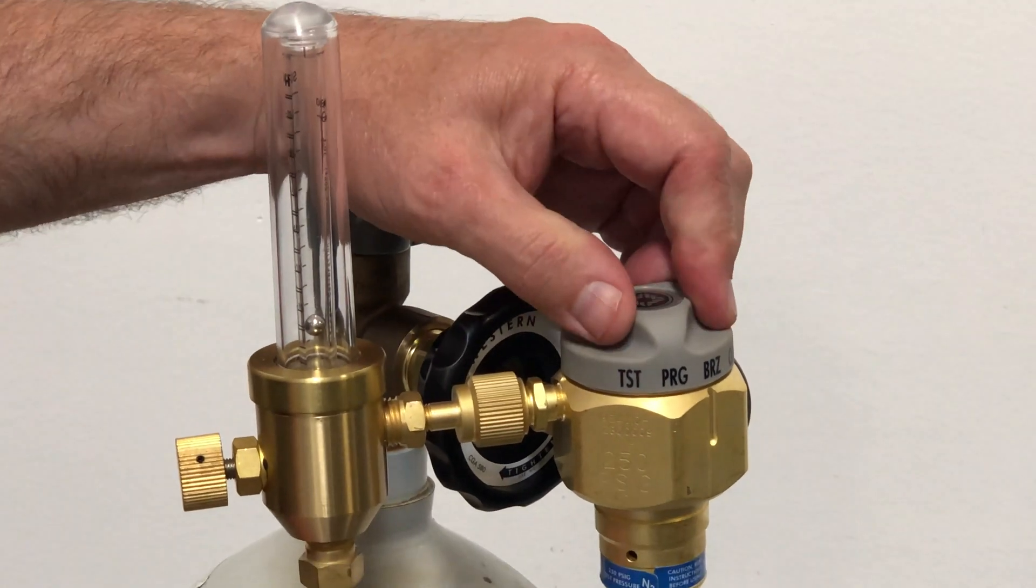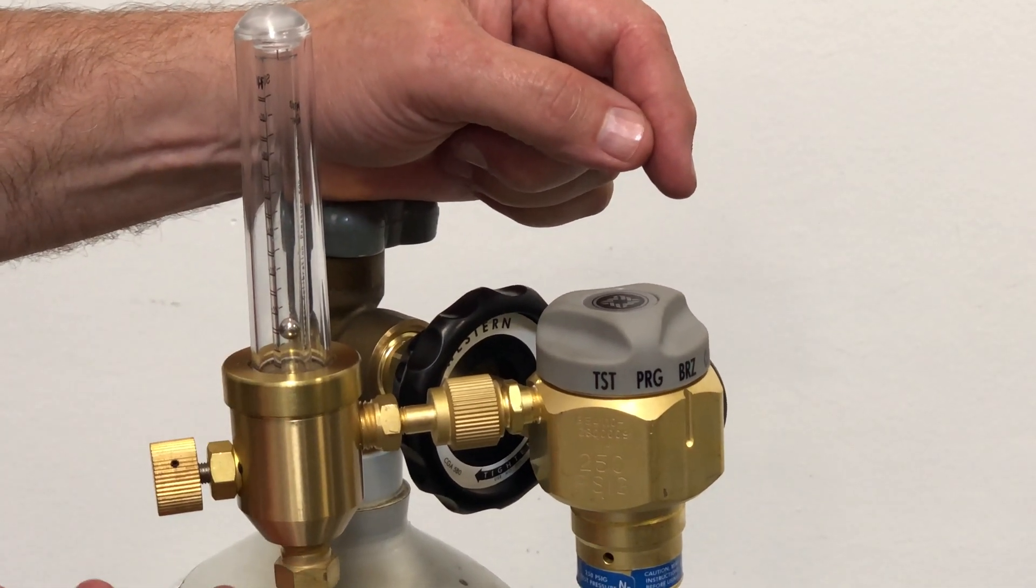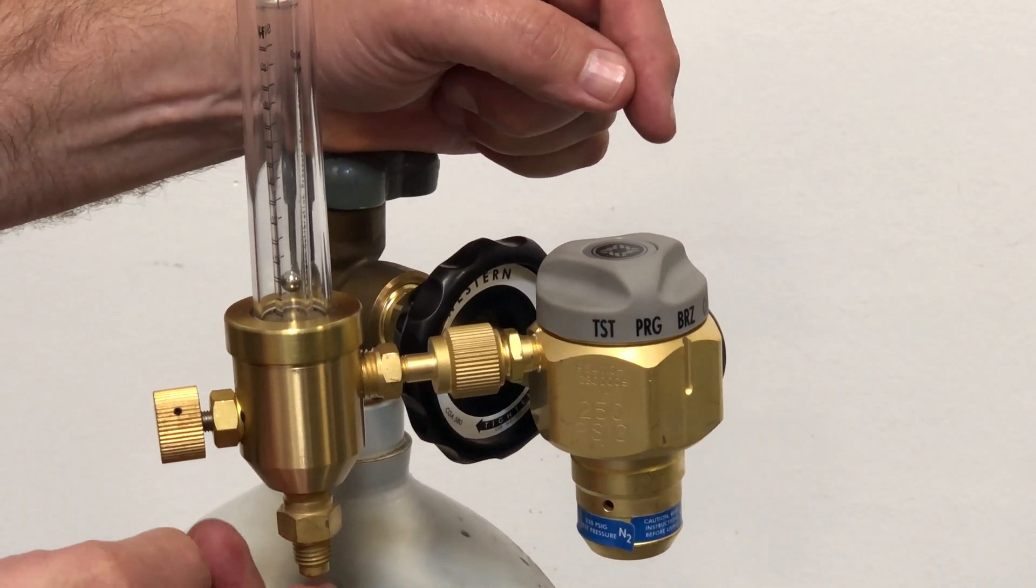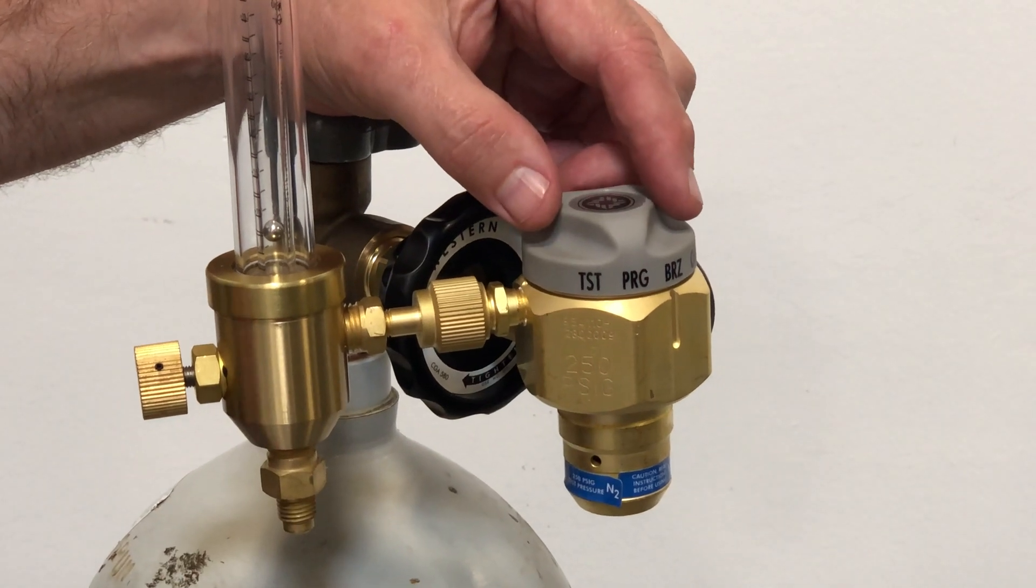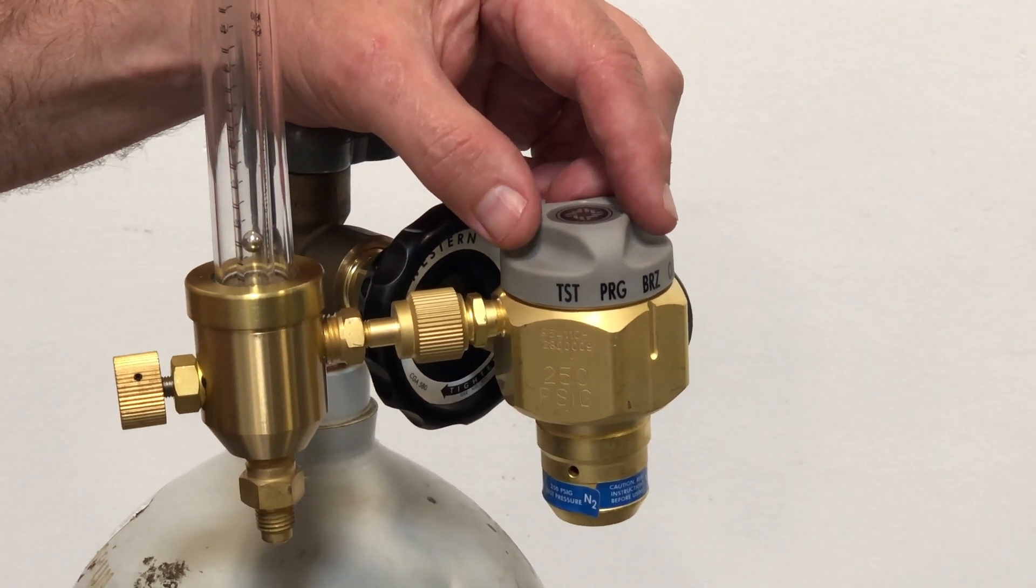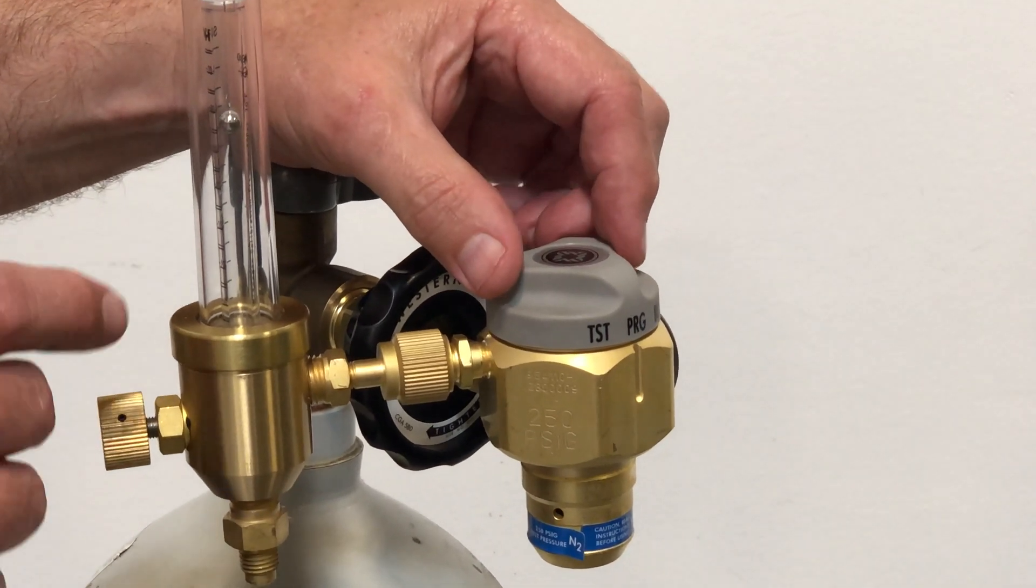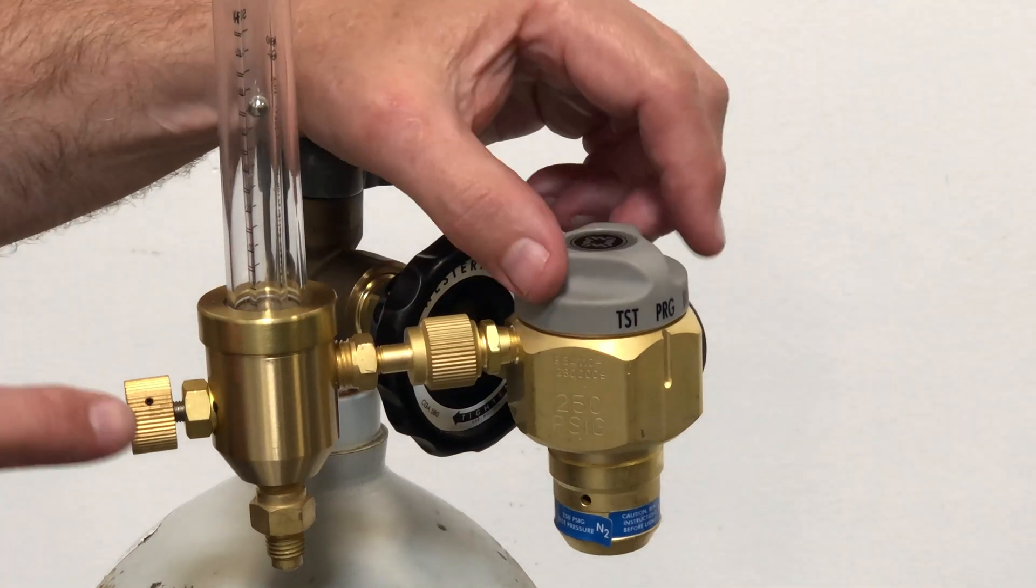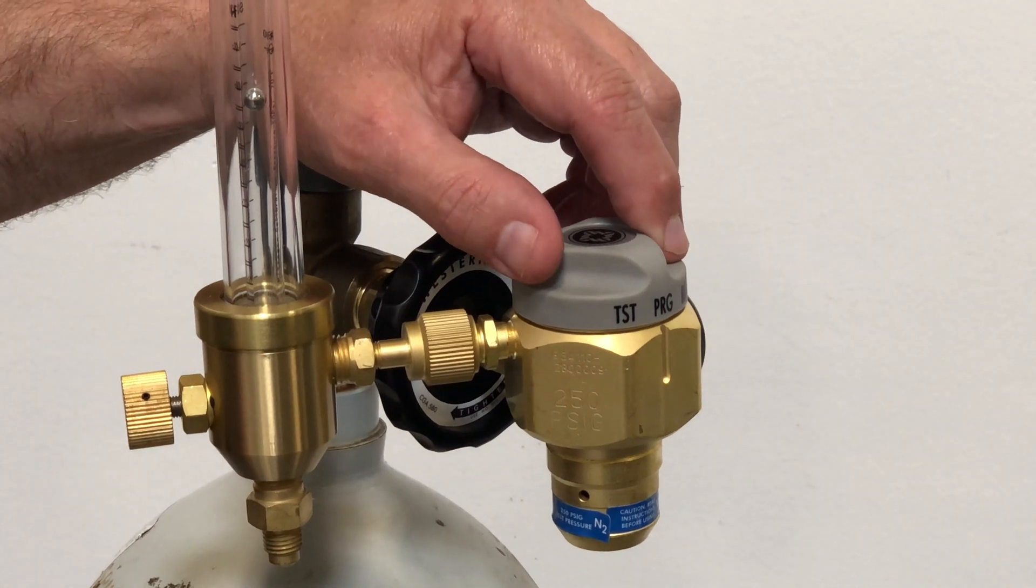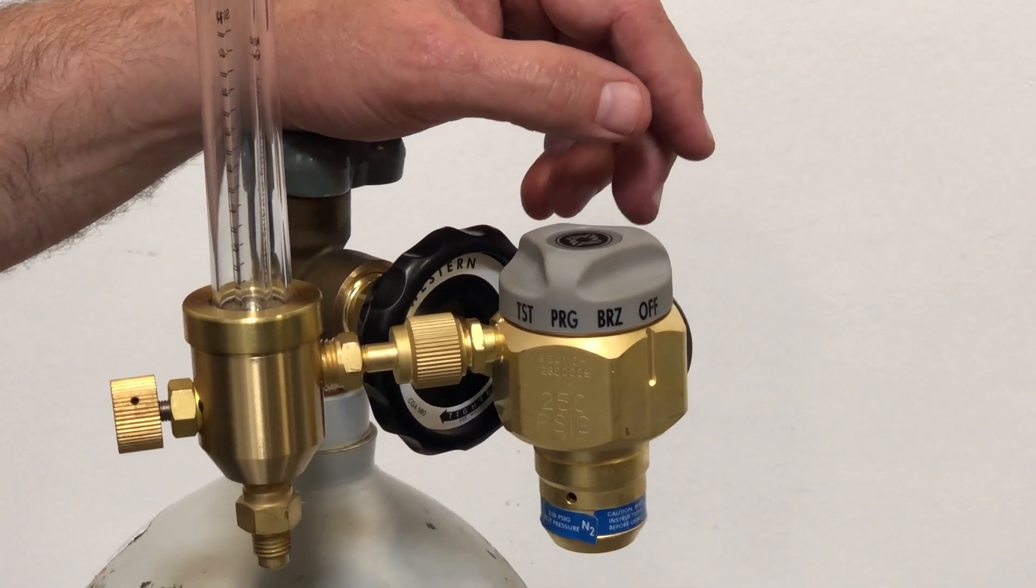Now when we get all done we're going to turn this to purge. Before I do that you can see this ball is floating. If I put my finger over this you'll see the ball will drop down because the flow stopped. You also hear the pressure building up because this regulator's set at 250 psi. When I turn it to purge, you can hear the flow substantially increased and we're now at about 60 standard cubic feet per hour of flow. This is to purge the atmosphere out so we want a pressure that's high enough to push everything out but low enough that it's not going to compress that moisture.